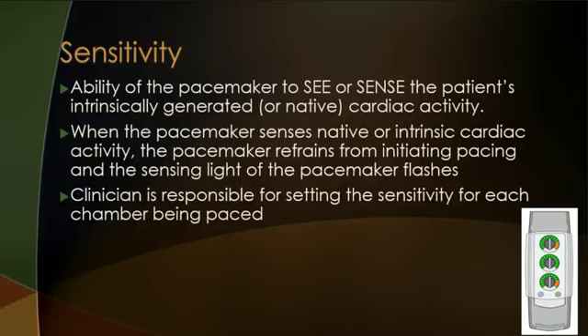So when you hear people talk about sensitivity and pacemakers, what they're talking about is the ability of the pacemaker to see the patient's intrinsic value or heart rate. When the pacemaker senses native or intrinsic cardiac activity, then the pacemaker will refrain from initiating pacing, and the sensing light of the pacemaker flashes. It will say it's sensing, but sensing and capturing are two different things. So the clinician is responsible for setting the sensitivity for each chamber being paced.